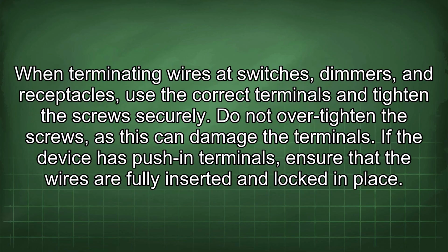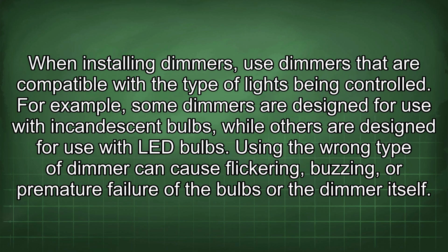When terminating wires at switches, dimmers, and receptacles, use the correct terminals and tighten the screws securely. Do not over-tighten the screws, as this can damage the terminals. If the device has push-in terminals, ensure that the wires are fully inserted and locked in place. When installing dimmers, use dimmers that are compatible with the type of lights being controlled. For example, some dimmers are designed for use with incandescent bulbs, while others are designed for use with LED bulbs. Using the wrong type of dimmer can cause flickering, buzzing, or premature failure of the bulbs or the dimmer itself.